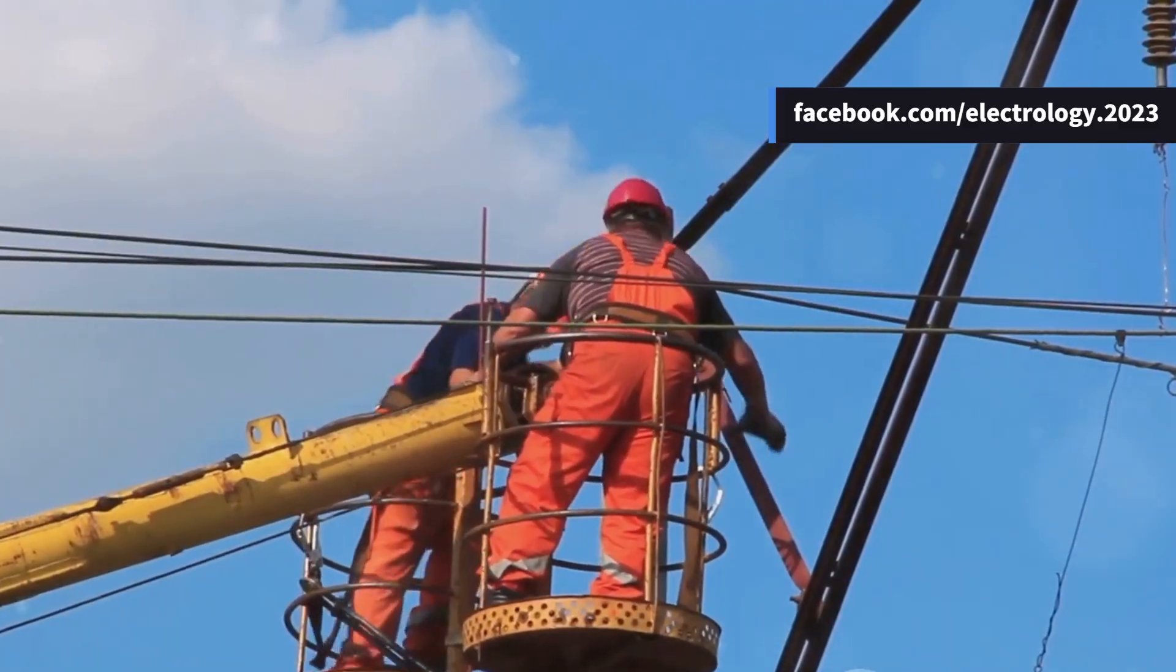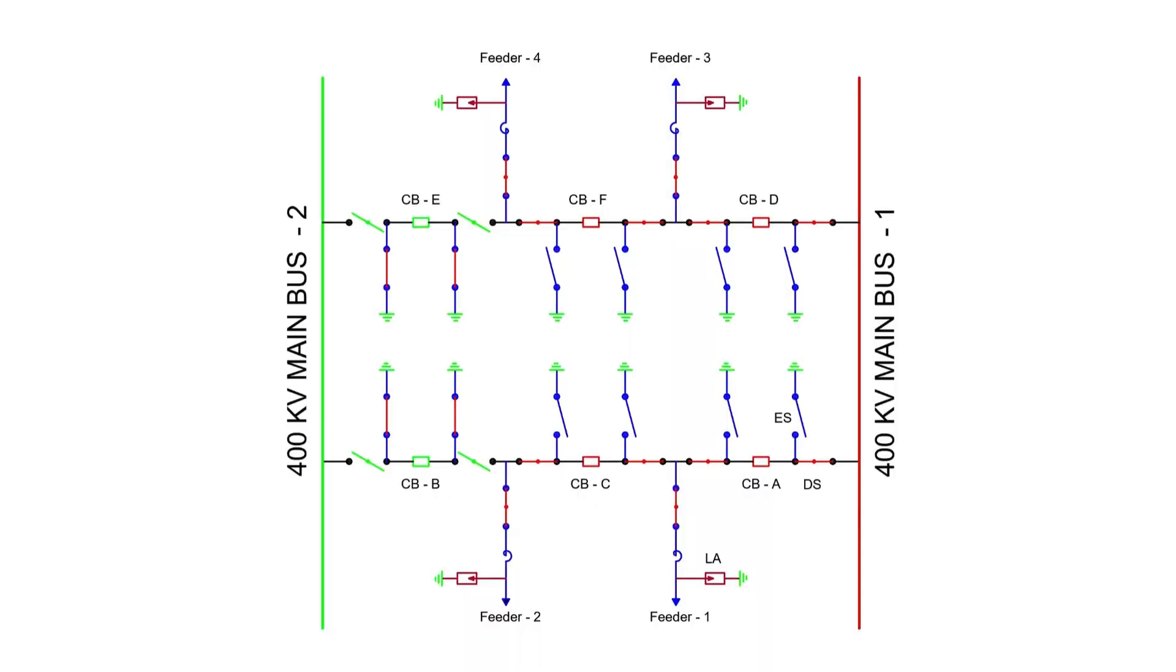Flexible maintenance. Either bus can be taken out of service for maintenance without interrupting power to the feeders. Maintenance of more than one breaker is also possible without any loss of service. There's no need for isolator operations when switching between buses as all three breakers remain closed during normal operation.